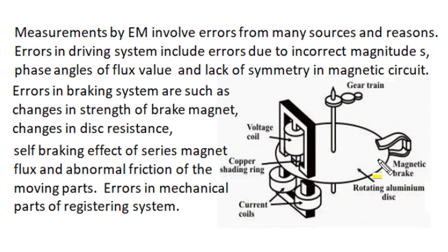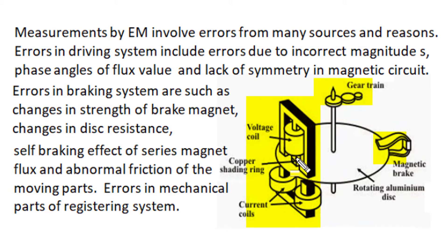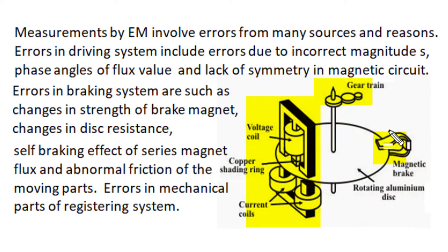Construction, design, and working of an energy meter has three different sections with many sources of error: the driving system, braking system, and registering system. In the driving system, error may be caused by incorrect magnitude and phase angle of magnetic field from voltage coil or current coil excitation, and distortion of magnetic flux or lack of symmetry in the magnetic circuit. In the braking mechanism, there could be changes in strength of the brake magnetic field and changes in disk resistance.